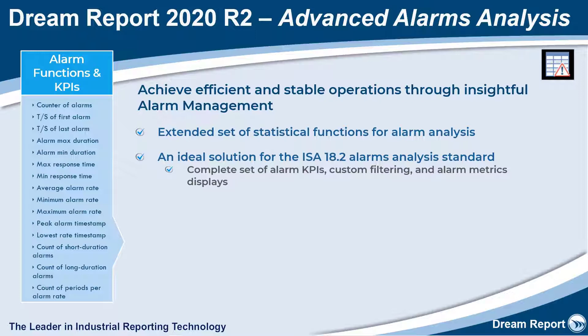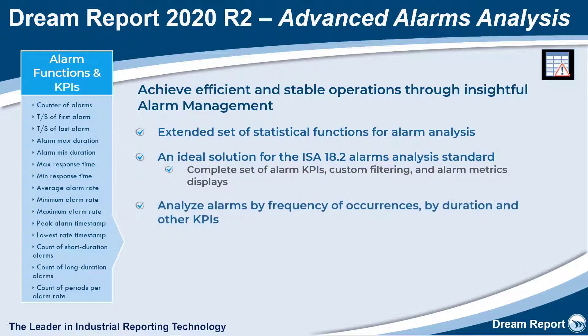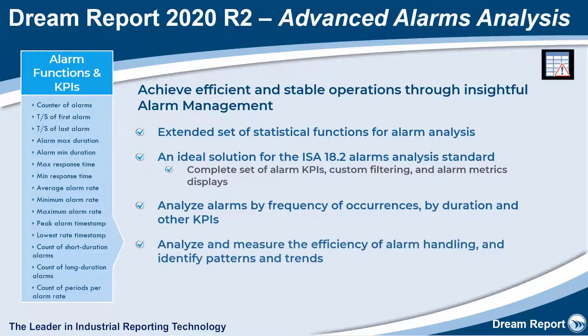You can analyze your alarms not only by the number of occurrences and durations, but also by alarm rates. This allows you to identify alarm floods, analyze and measure the efficiency of alarm handling, and identify patterns and trends. These alarm metrics can be automatically fed back to your HMIs, and using the new Notifier feature, notify users of alarm KPI exceptions.